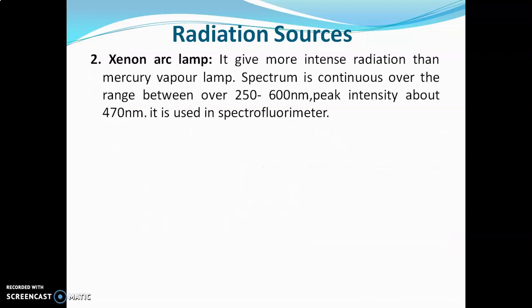The xenon arc gives more intense radiations than the mercury vapor lamp. Its spectrum is continuous over the range of 250 to 600 nanometers, with peak intensity at about 470 nanometers. It is an expensive lamp, generally used in spectrofluorometers. The advantage of this lamp is that it gives a continuous spectrum.